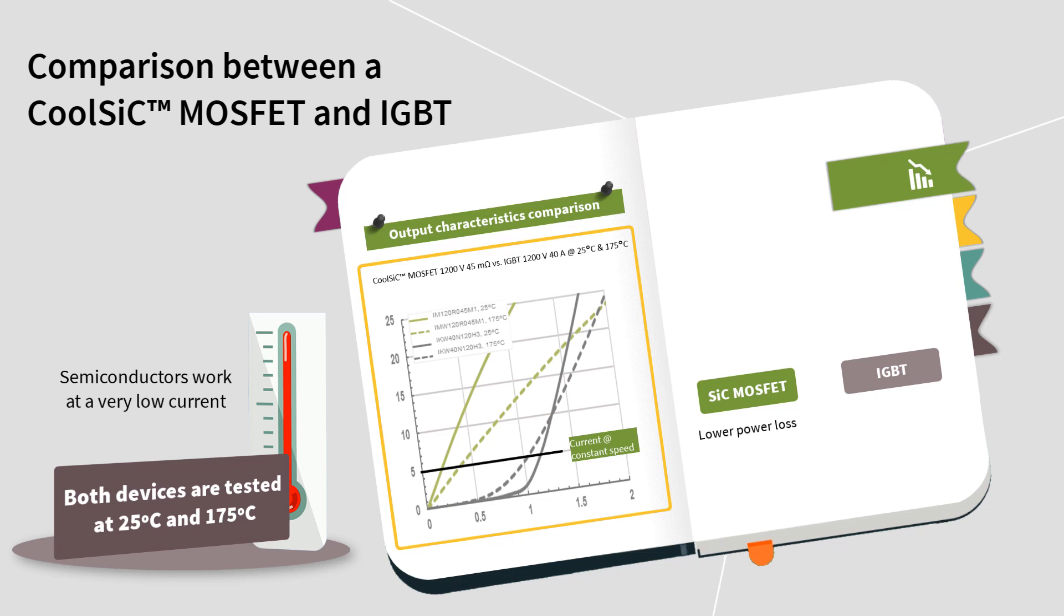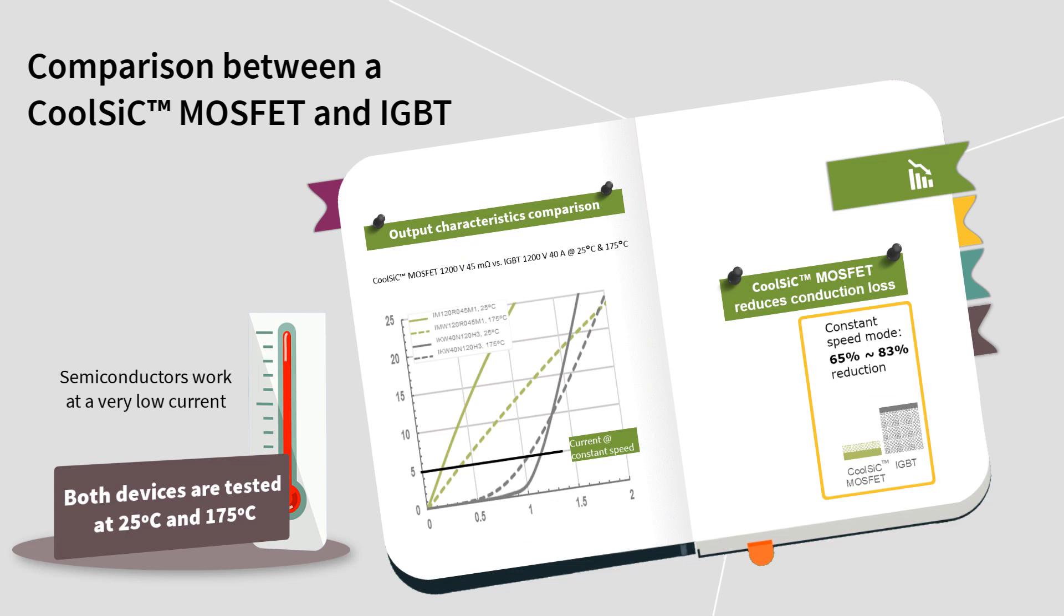This happens because SiC MOSFETs have a resistance behaviour in which low current results in low voltage. In the case of IGBTs, due to the knee voltage, the voltage across the device will be over 4 times higher than in a CoolSIC MOSFET. Finally, here you can see that, in a constant speed mode, CoolSIC MOSFET reduces conduction losses up to 83%.